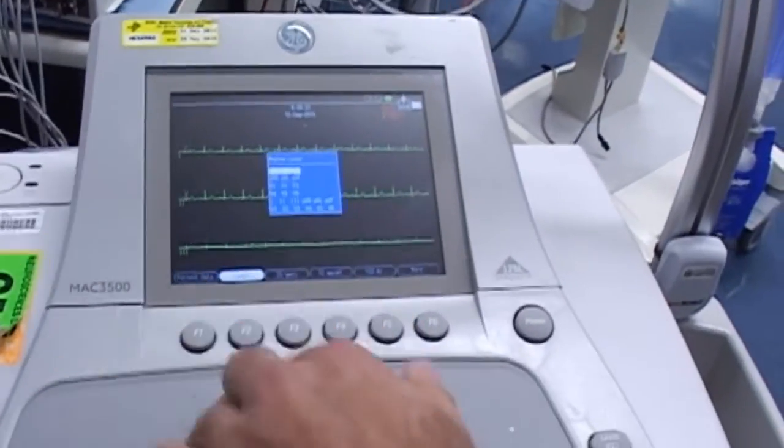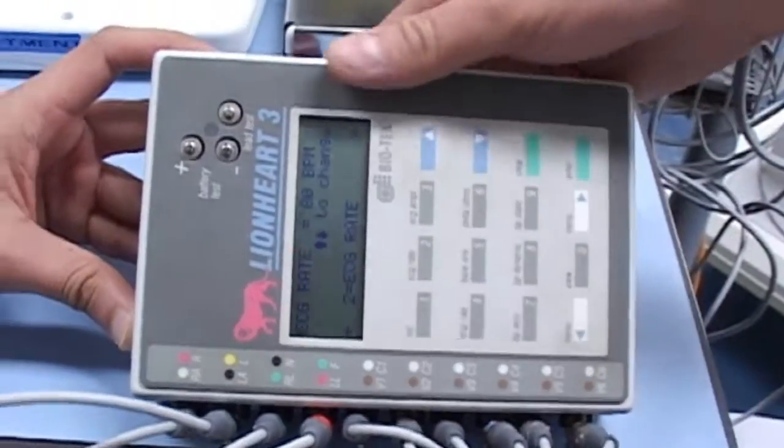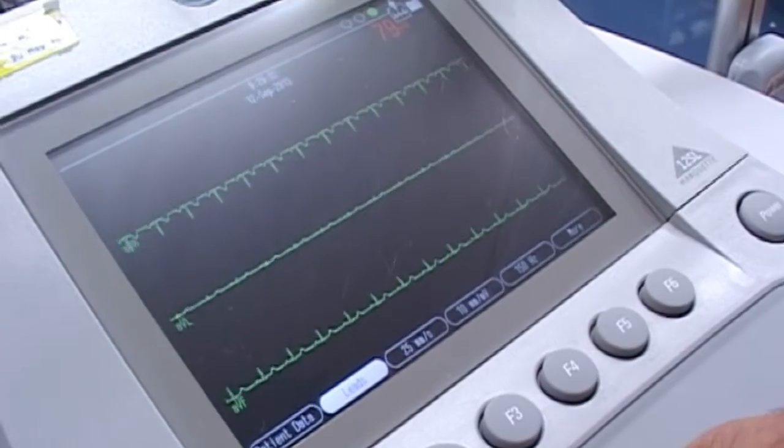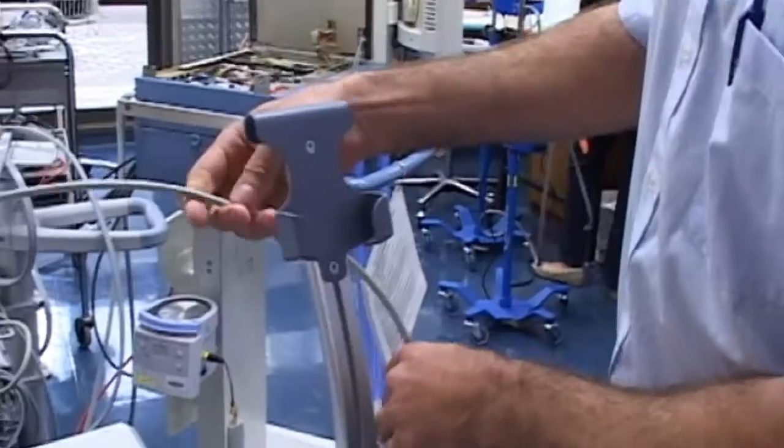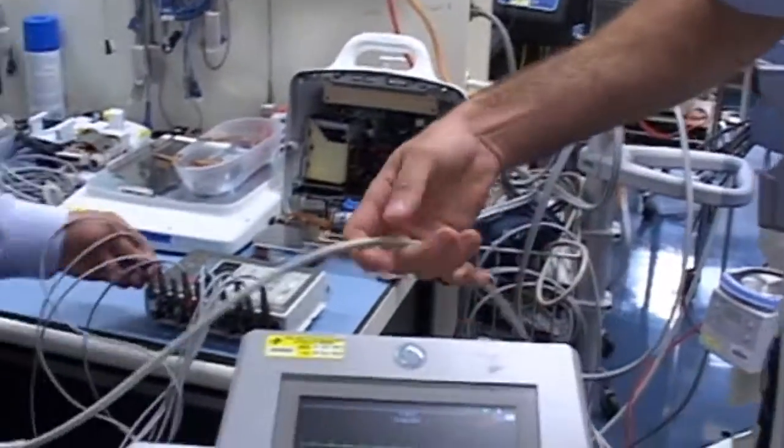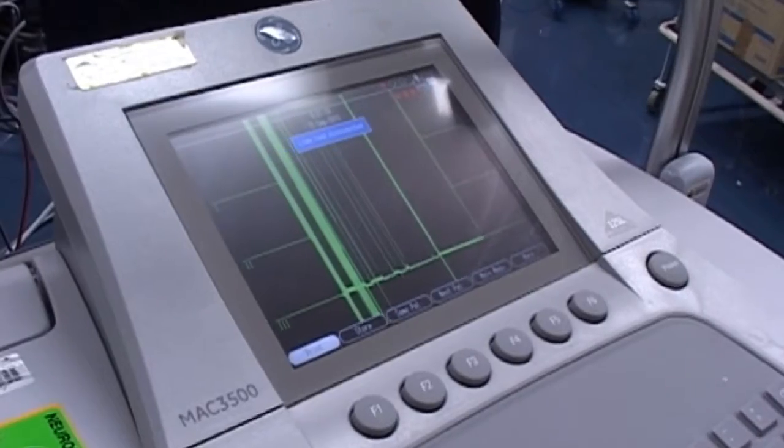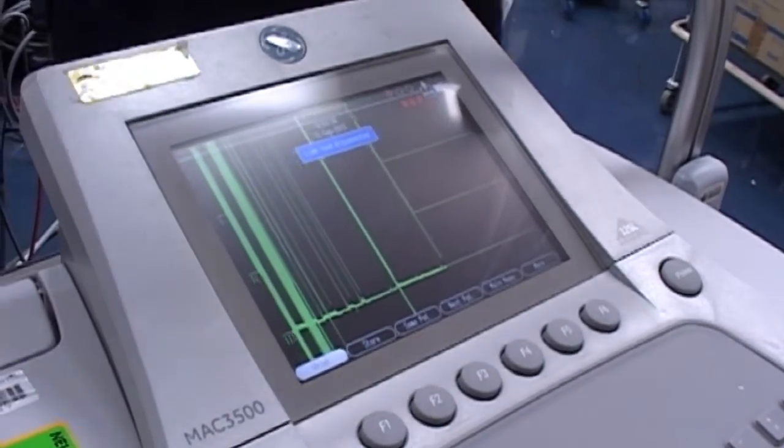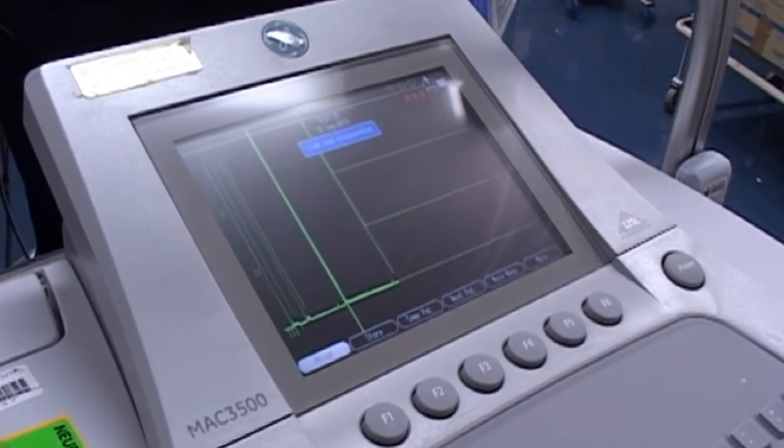There is a definite line between what's a medical device and what's not a medical device. At the end of the day, we have to make a clear understanding that anything that's connected to a patient is a medical device. A medical device has to meet a certain criteria, has to be tested at a certain interval under any ISO standard, so it can't be treated as just your standard computer.